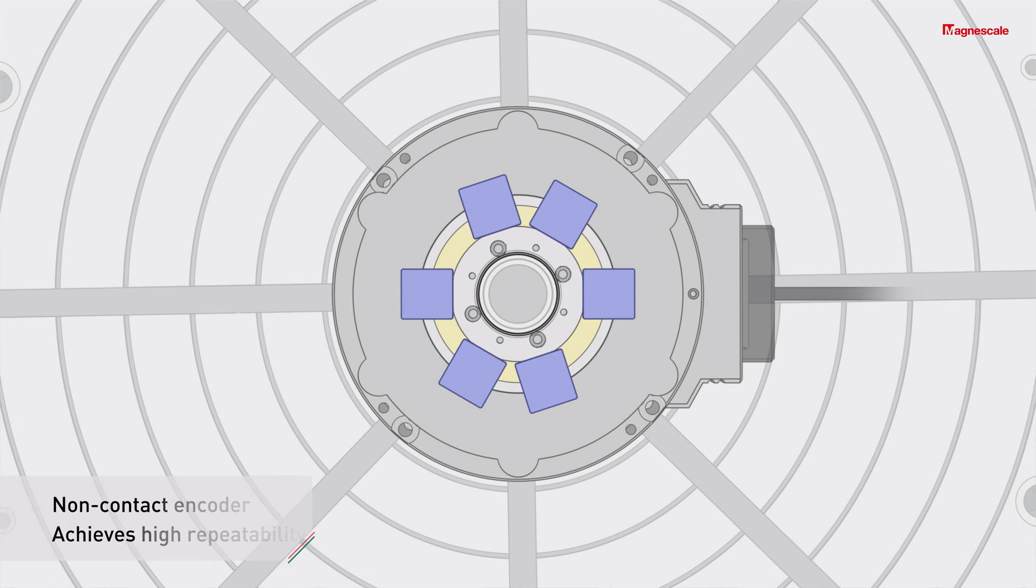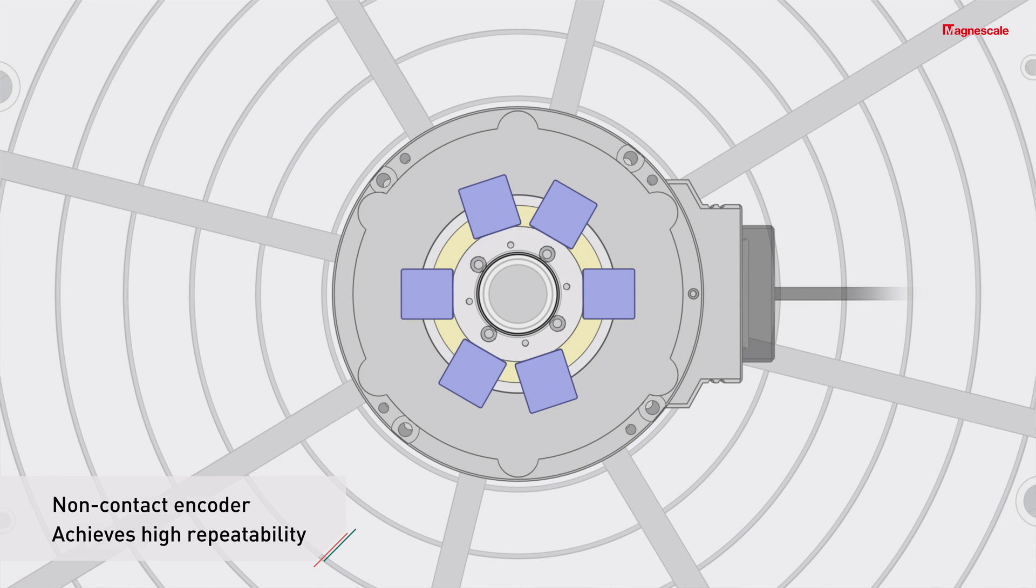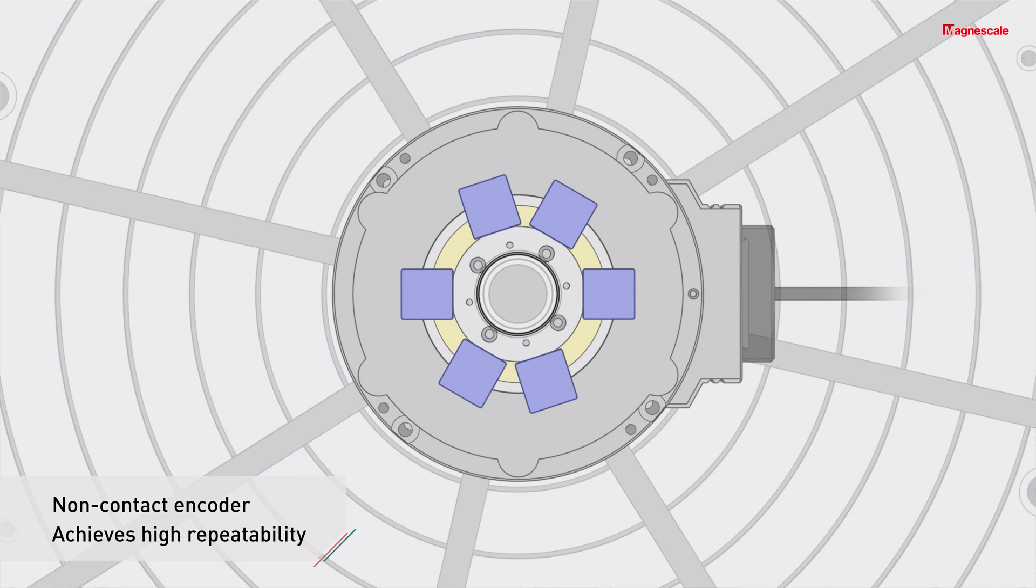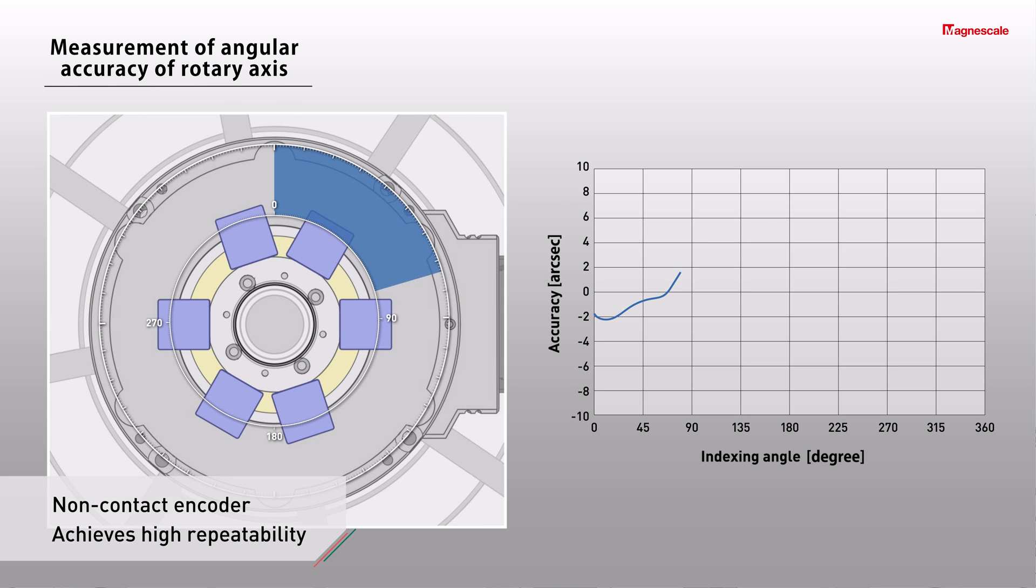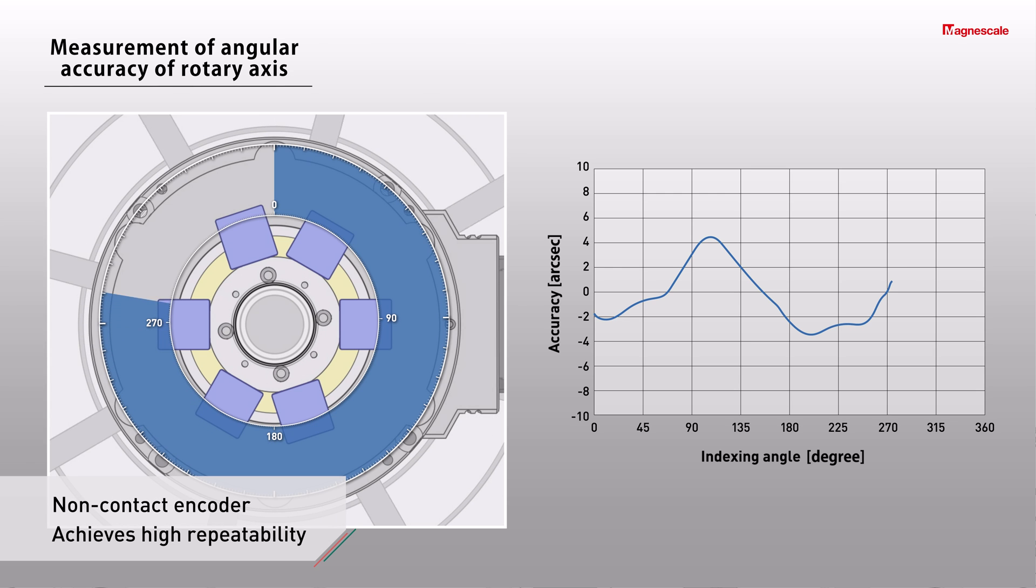Measurement by the non-contact encoder minimizes any impacts on the rotary axis. Thus, higher repeatability is realized and reliable compensation of all errors in each angle is supported.